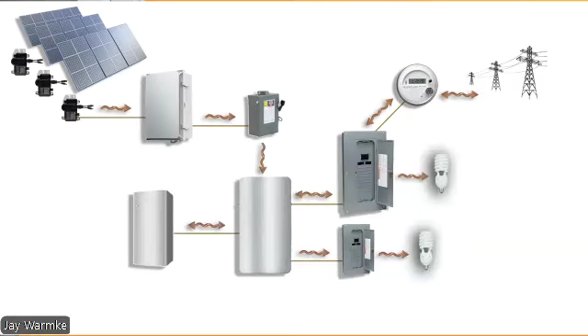And you could have a main load panel, a critical load panel. You could have whole backup, whole house backup, or only critical load. And I know they don't like to use the term critical load anymore. Typically backup load, because I guess somebody got a burr under their saddle about not all these loads are critical. You know, it's like in a hospital, it might be critical, but your coffee maker is probably not a critical load. It's a backup load. Well, for me, it's a critical load, but my garage door opener, not so much, if I had a garage or an opener.